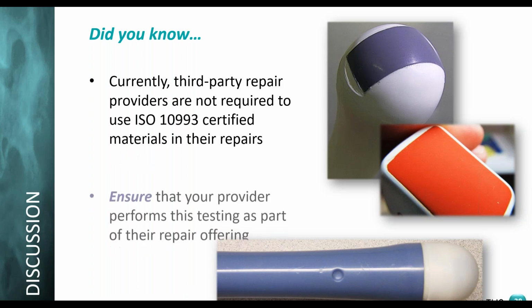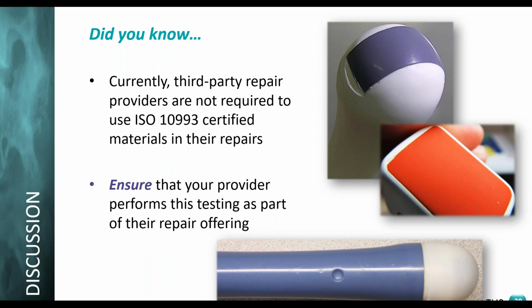So we are not required to use ISO 10993 parts. One of the things with this particular probe, when I was talking about adhesives and chemicals, that's a GE RIC 5-9-D. About a year ago, we got in a rash of those, dozens and dozens every week. Another third-party provider was using an adhesive that was not tested for a disinfectant device called Trophon. The Trophon device was breaking down their adhesives, and these probes were coming apart inside patients, which is a very bad thing. Because of all the testing that we do, our materials are compliant with Trophon.